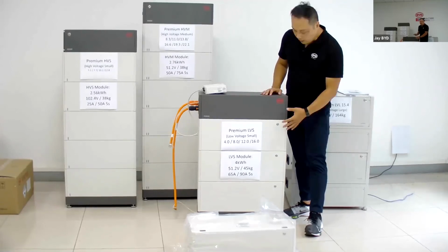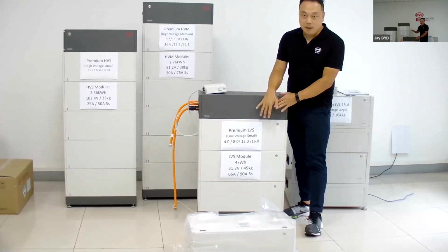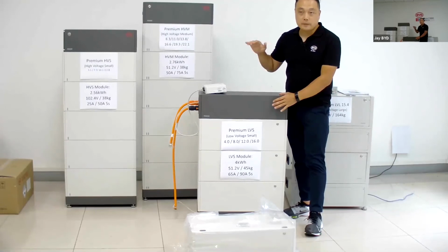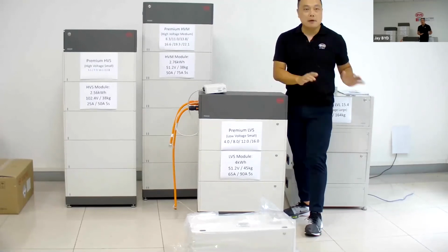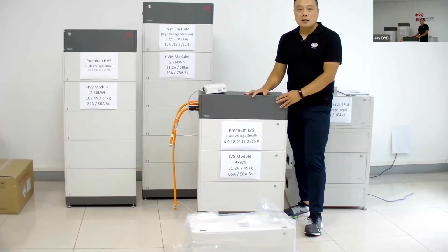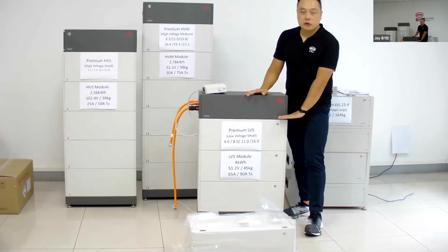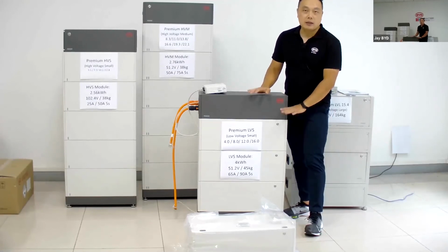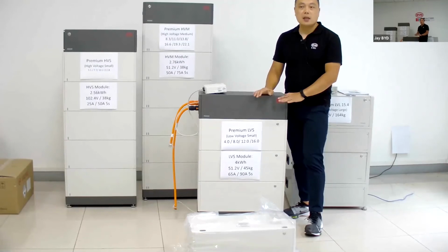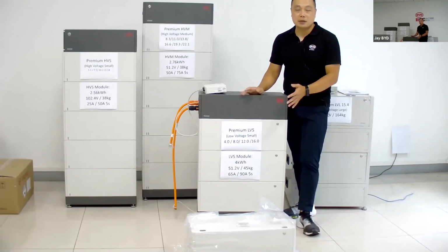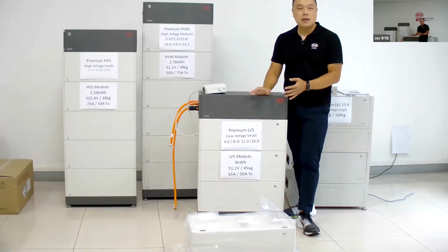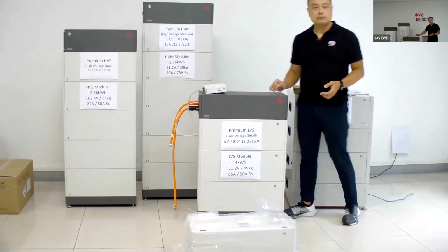So single tower from 1 module up to 6 modules. Multi-tower in parallel, each tower we recommend 4 modules in parallel connection. More battery modules is acceptable, but it won't increase output power more than the 4 modules.